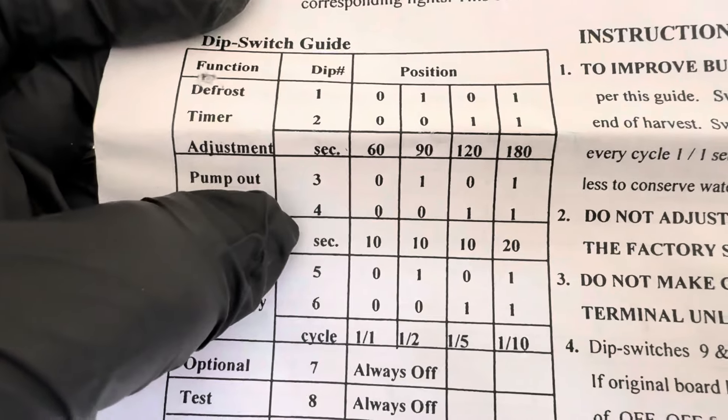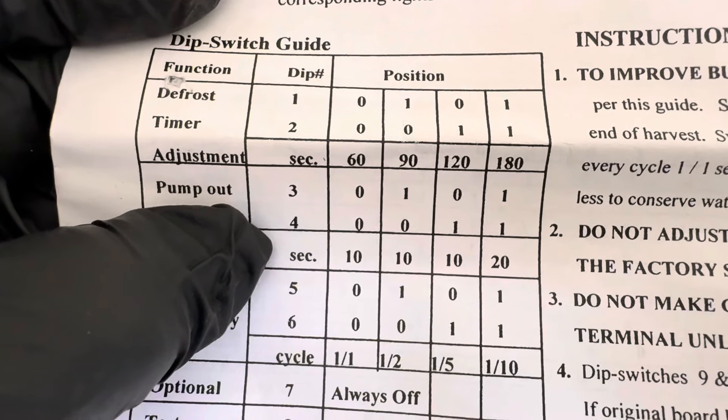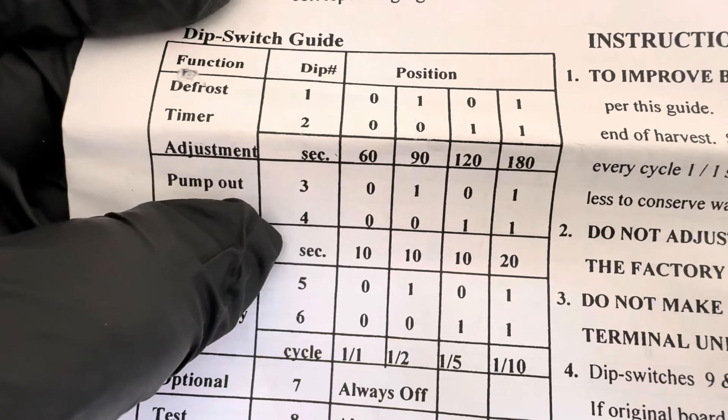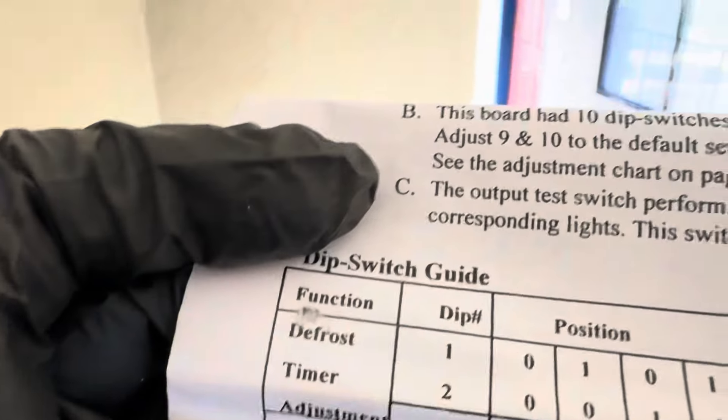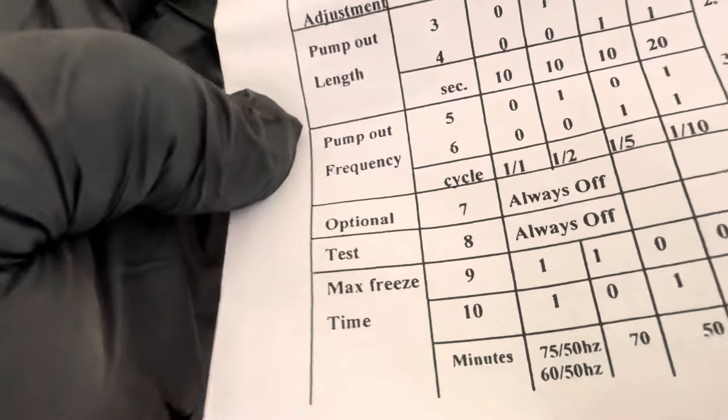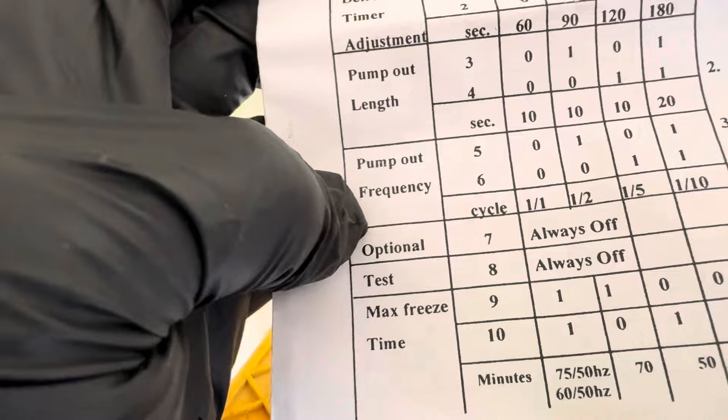Your pump out length, DIP switches 3 and 4. I keep those at zero, I keep those at zero. This one switch, with 3 on, 4 off. So that's 10 seconds pump out frequency.